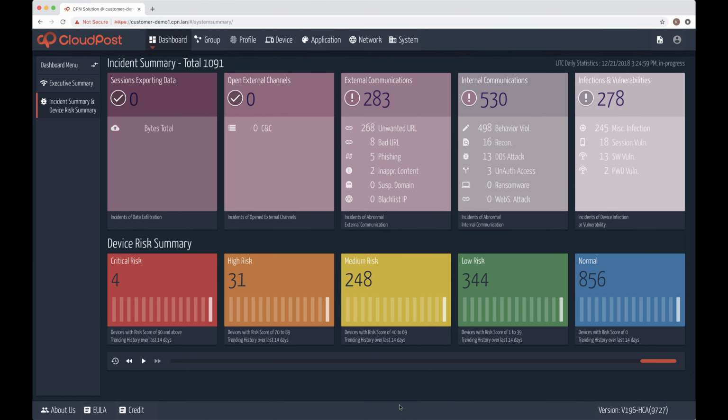The other data point that we use to calculate risk is industry-known vulnerabilities and manufacturer recalls. So some examples, we use FDA recall, MD Viper. We can also read in MDS2 forms or tie into ICS-CERT. Let me show you an example.